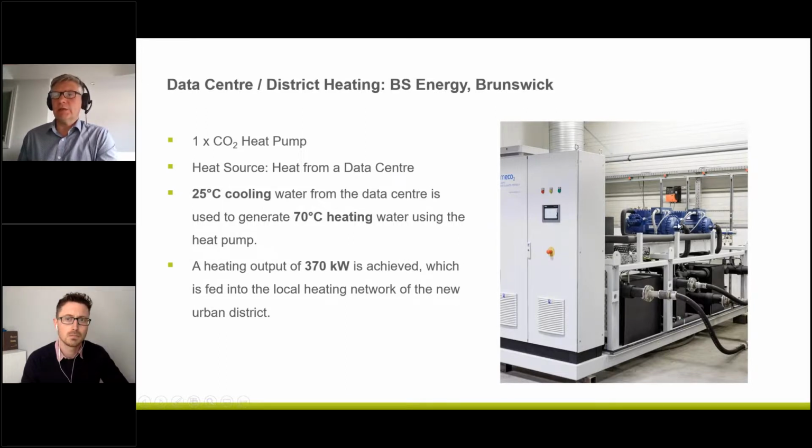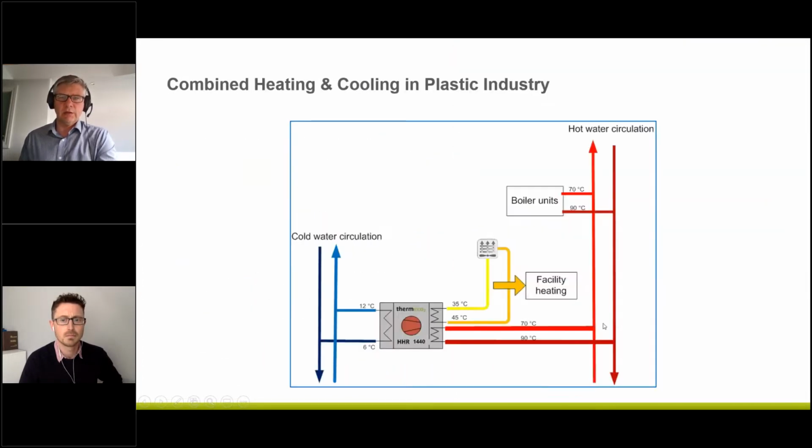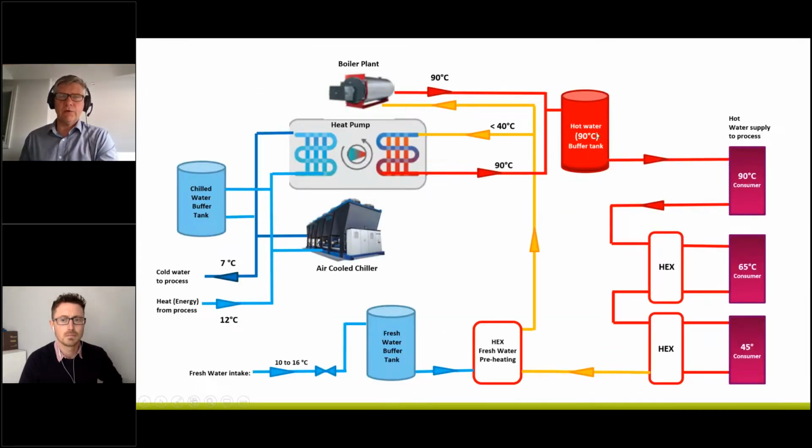And depending, basically, on sequencing, that's why they've got a number of compressors as well, because you can load them up partially, and as more load comes on, more compressors can be sequenced on and off. And with the VSD, it'll ramp up with the partial loads. Depending on system design and the heating required, maybe splitting it up into two different heat pumps as well. So again, I have to look at system design, but between the VSDs, the various different compressors and even compressor sizes, and in addition to that, the buffering can help with loading and taking out these peaks and troughs, say if there's low demand on the system and then high demand on the system.